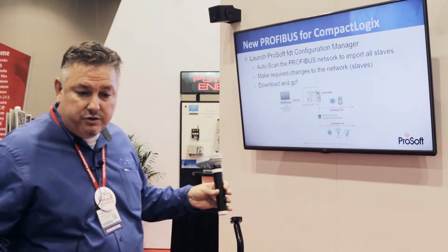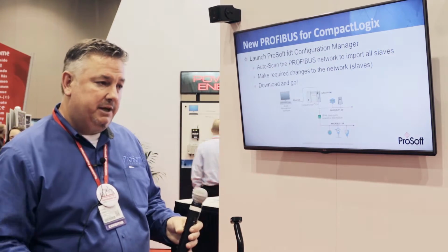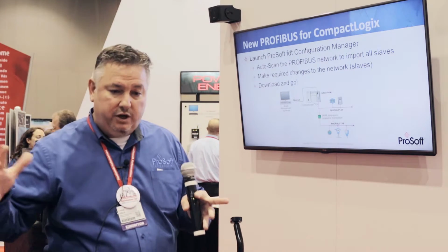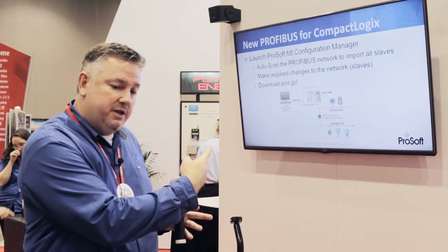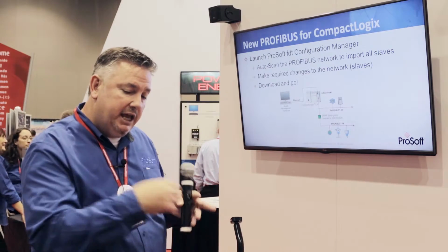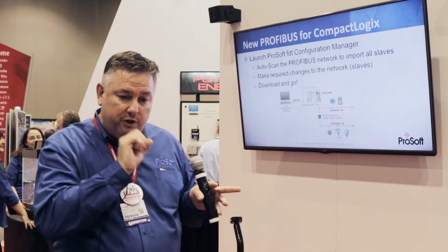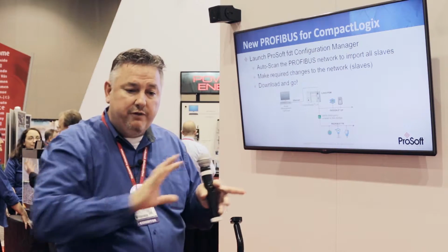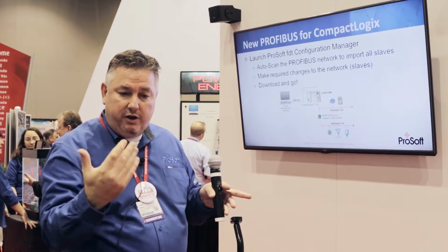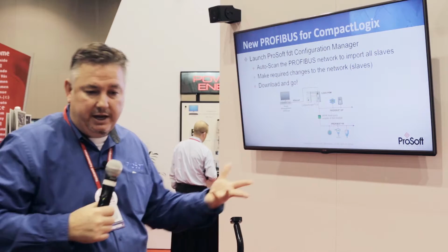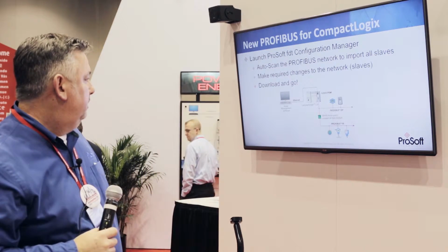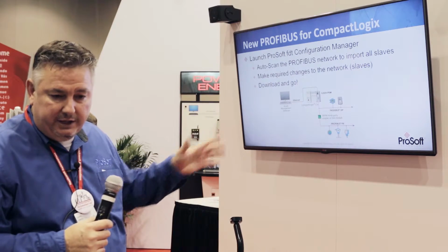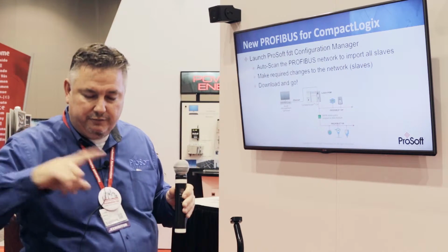So yeah, it has the auto scan feature. What's really nice about that is, say you have a system out there and you want to try out another master on your system. Well, you can bring in this master here and you can hit auto scan, and it's going to go out and do a broadcast, and it's going to bring in all your slaves, however they're configured. So it'll bring in all your slaves, how they're mapped, so they're automatically mapped. You make required changes, you download, you're done. Now you can still do it the other way, the typical way of dragging over and configuring that kind of thing.